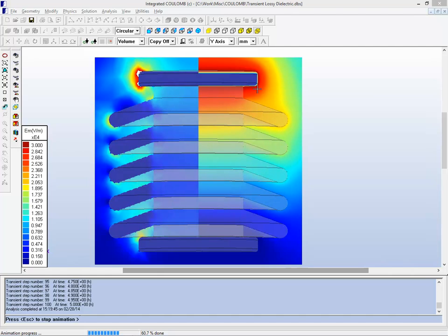So as time progresses, instead of the high field being right at the edge of the top cap, the high field instead is around the tips of the insulating sheds, and the space in between the sheds is showing a high field as well. So when you talk about high voltage DC and insulators, you have to realize that time frame is important. No matter how small the conductivity of a material is, it is not zero. That means that eventually the analysis will look like a conductivity analysis.